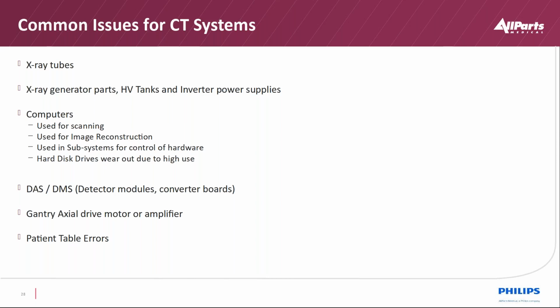So we're using hard drives quite hard with regards to that raw data drive set. We're moving a lot of data to them quickly. They're 10 or 15,000 RPM drives, and they're on 24/7 typically, so they will wear out. In the case of newer systems, they may be using solid state drives for that functionality. Then we have our detector elements; the crystals in those detector elements will degrade under radiation hardening. The converter boards behind them are more integrated, so the whole module may be replaced or aged out. Typically the center modules go first because they see more radiation than the edges do.